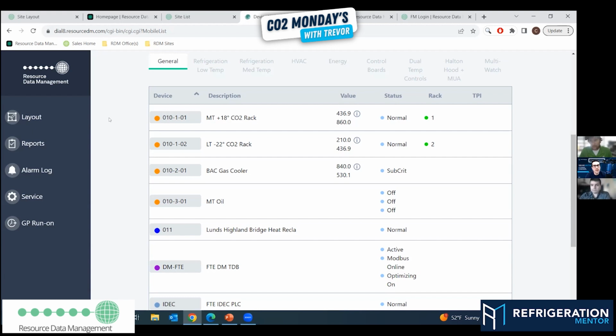And I like what you brought up there. Do you feel, or have you noticed, technicians trying to fix a system issue through the controller when it's an actual mechanical issue? Have you been noticing that? I see it a lot. Yeah, and I've been seeing that more and more too. Guys call me and walk through it. So you cannot troubleshoot a system just through the controller.